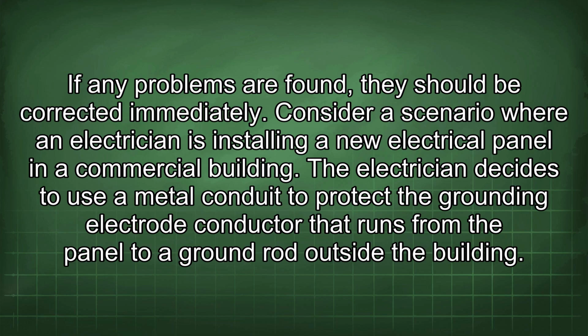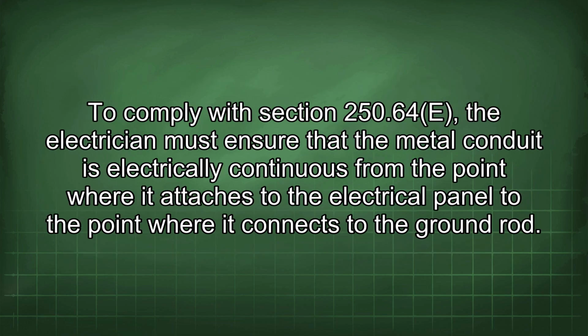Consider a scenario where an electrician is installing a new electrical panel in a commercial building. The electrician decides to use a metal conduit to protect the grounding electrode conductor that runs from the panel to a ground rod outside the building. To comply with Section 250.64(E), the electrician must ensure that the metal conduit is electrically continuous from the point where it attaches to the electrical panel to the point where it connects to the ground rod.